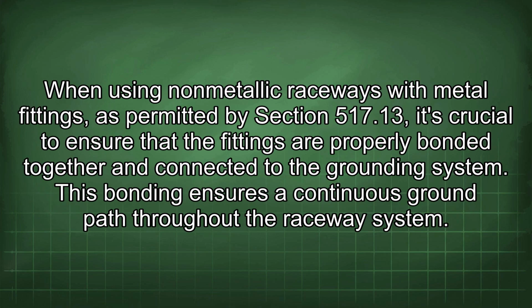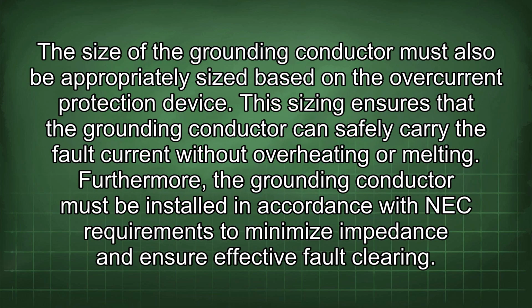When using non-metallic raceways with metal fittings, as permitted by Section 517.13, it's crucial to ensure that the fittings are properly bonded together and connected to the grounding system. This bonding ensures a continuous ground path throughout the raceway system. The size of the grounding conductor must also be appropriately sized based on the overcurrent protection device. This sizing ensures that the grounding conductor can safely carry the fault current without overheating or melting. Furthermore, the grounding conductor must be installed in accordance with NEC requirements to minimize impedance and ensure effective fault clearing.